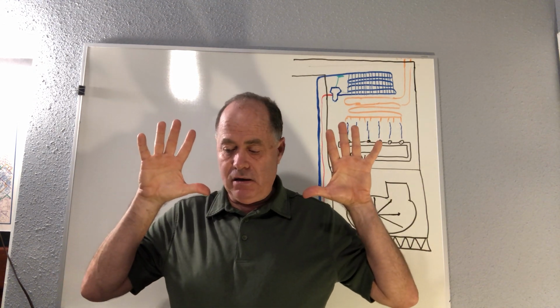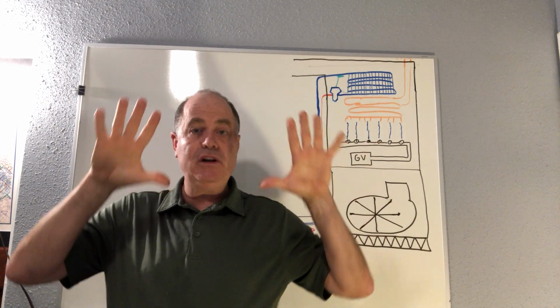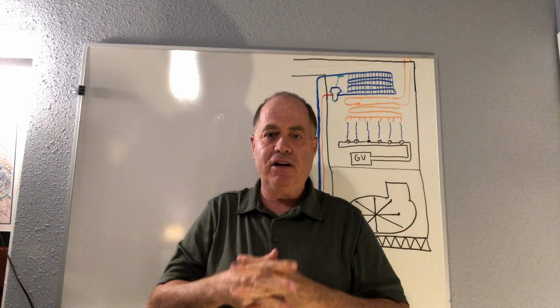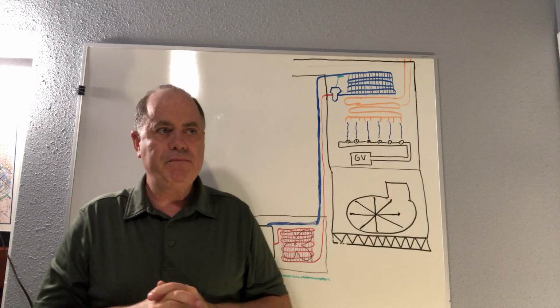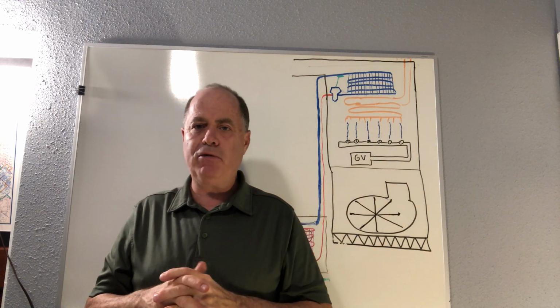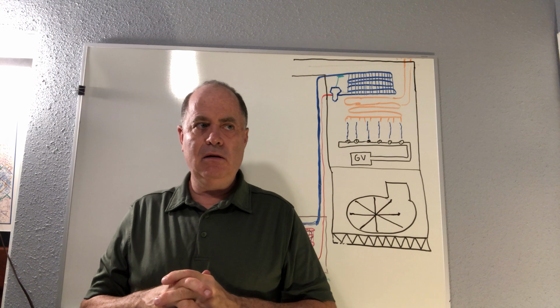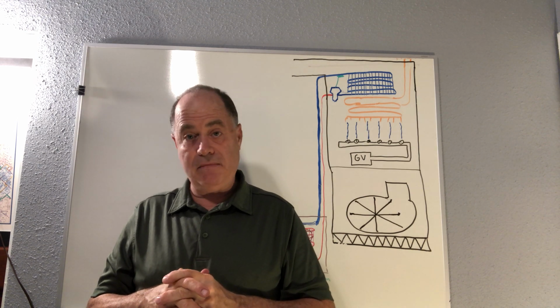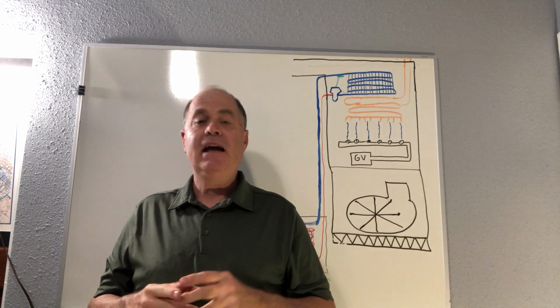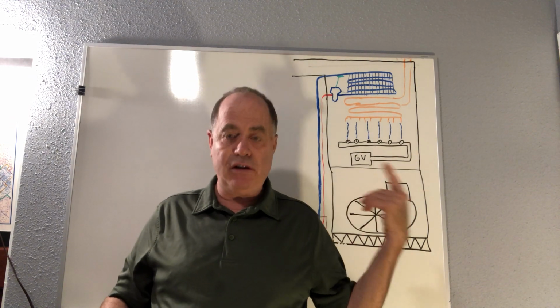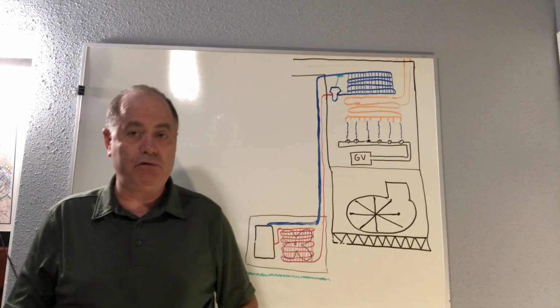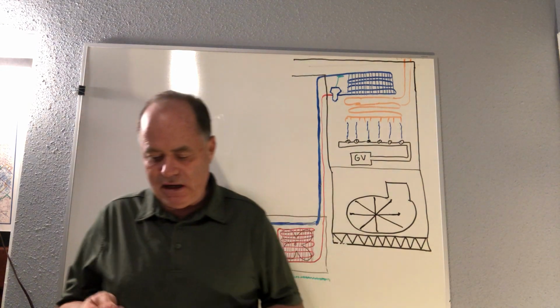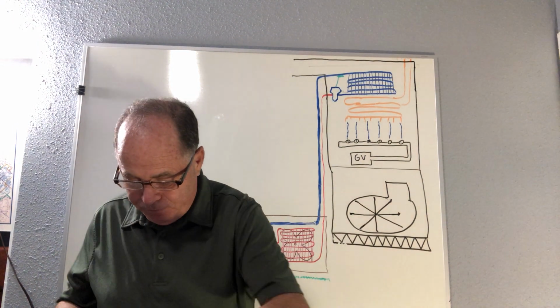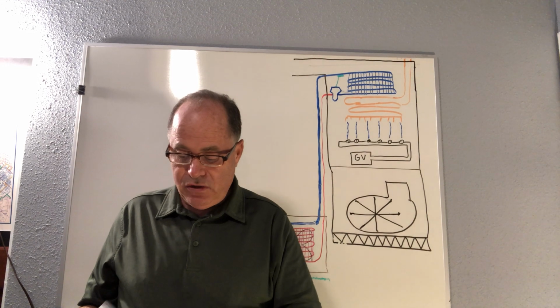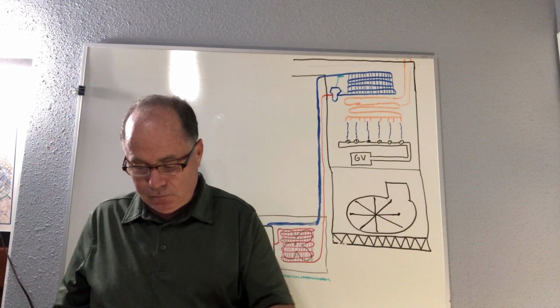They have these type of industrial heaters where you can take air from the outside, heat it up, and blow it in, and the products of combustion go in there too, into the space. But it's more like a temporary heating thing. And again, no one has the possibility or shouldn't be sleeping there, and they don't ever recirculate any of the air, so nothing really builds up. It's just kind of in and through and out. Okay, so we have that industrial type of heating. Okay, must by code use 100% fresh air.